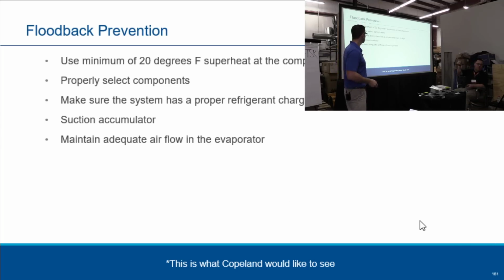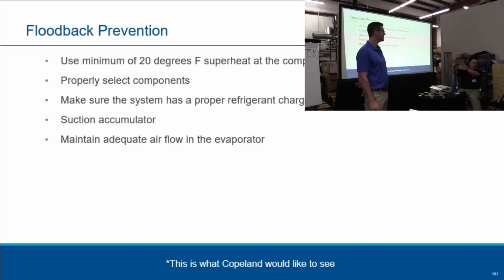The only thing I want to add, we don't really dictate superheat so much or subcooling because we don't know where that compressor is going or in what application. That superheat we're setting there is if you're having trouble with liquid flood back, but at a high load condition, because we lose more compressors on low load than we do on high load. At night when it cools down and you're at low load, you have more opportunity for that liquid refrigerant. Just food for thought. Awesome.